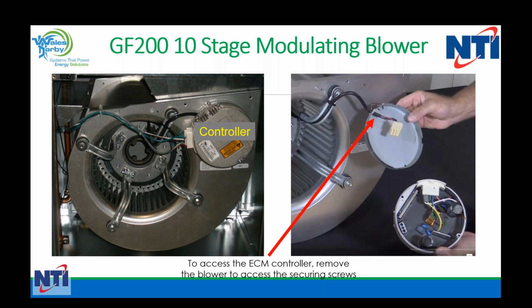To remove the blower, it will be left or right. So take either one of the doors off on the left or the right, and the blower will slide completely out. So if you're in tight quarters and your unit's going to have minimum clearance, let's say on the left side, and you're bringing your return air to your right side, make sure you can remove that right side duct to remove the blower if necessary.